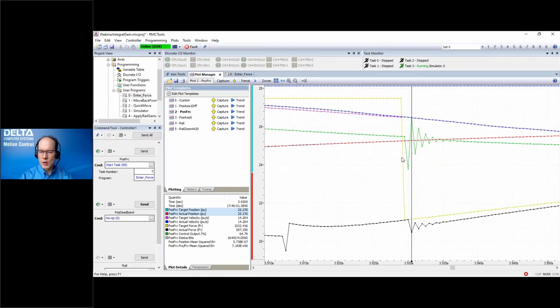If we zoom in more, we see our control output. It's kind of bouncing up and down all over the place. So this is kind of a shaky transition. But what we can do is look at the control output right here. Control output says 41, and then the control output bounced down to 4. So we're missing about, let's see, 41, 42 minus about 4 or 5.